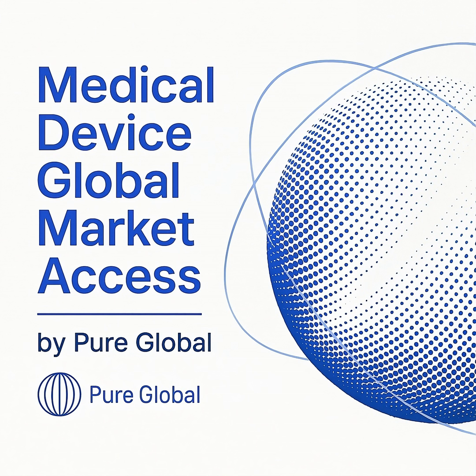This leads us to another key area: post-market surveillance, PMS, and post-market clinical follow-up, or PMCF. Regulators are increasingly rejecting submissions with weak or absent PMCF plans. Simply stating that no PMCF is necessary is rarely sufficient.